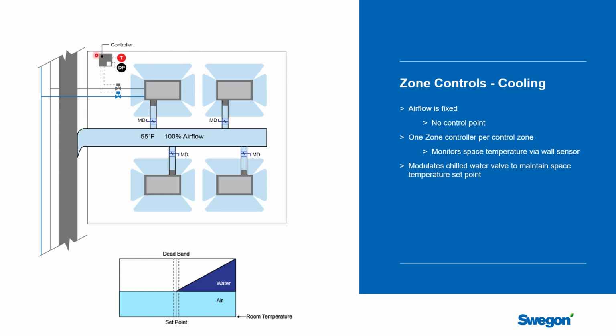But a better way to look at it is to divide the building up into control zones. And there will almost certainly be multiple beams within that control zone. And so there will be one unit controller from the building automation company that's servicing this. This box here would be our control zone. If it was a classroom, that would be very obvious. In an office space, an open office concept, this might be at least one of these 4 facades, and then maybe 1 or 2 in the core. And then if you had specialty spaces like conference rooms or private offices, they might also be control zones. Same rationale and logic you would use if you were dividing a building up for a VAV system.